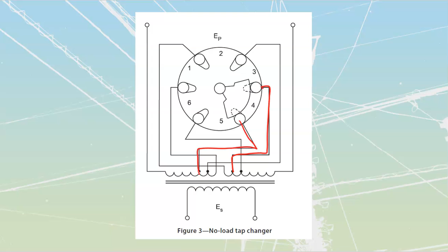If I follow my total lines all the way through, let's say this is my source voltage. The voltage doesn't matter much right now, but it's the high voltage side because it's got more windings, and therefore it's the low current, which makes it easier to switch. I can see I'm going through 1, 2, 3, 4, up and through, then my current path completes through here, and then goes 1, 2, 3, 4, 5 on this side, and back out to my source voltage.